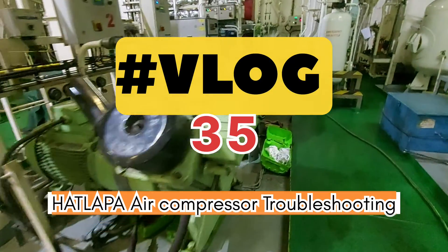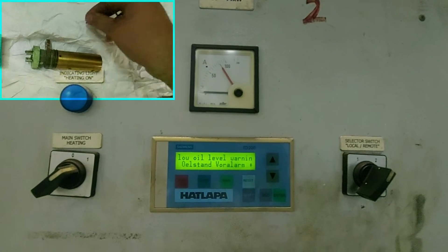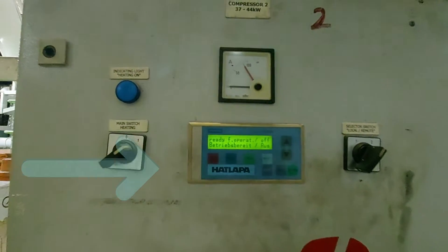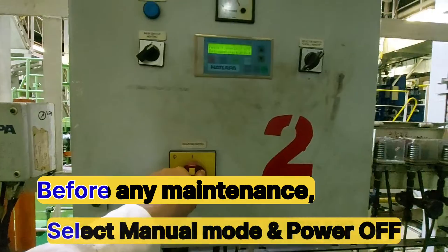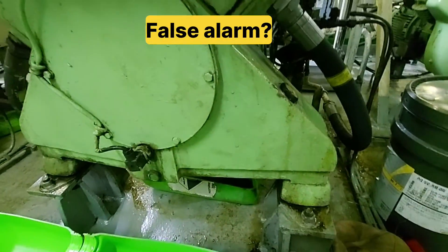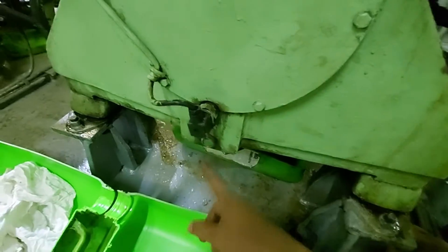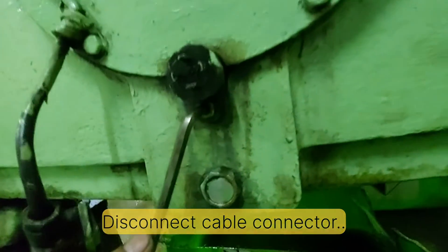Hello guys, once again welcome back. This is Lawrence. I hope you all are good. Today's video is on the HATLAPA compressor. In this video I will overhaul the level sensor for the low oil level alarm. As we can see, I attended a fault alarm on the compressor display for low oil level. When we accepted this alarm, we immediately checked the oil level and found the oil level is good. So what could be the reason for this alarm? Most probably the level sensor. So let's see how to overhaul the level sensor and what kind of sensor we have, and what is inside the air compressor. Let's start.